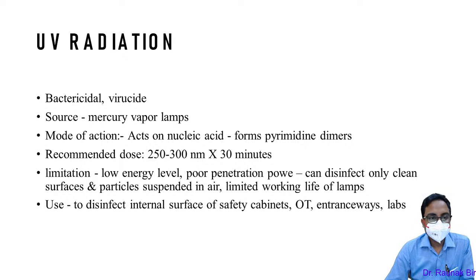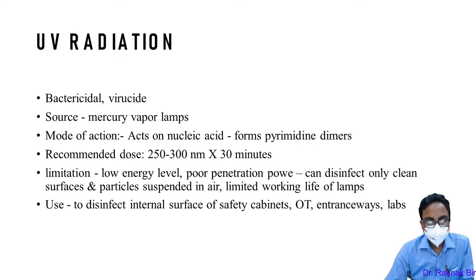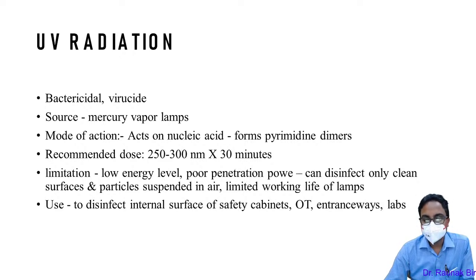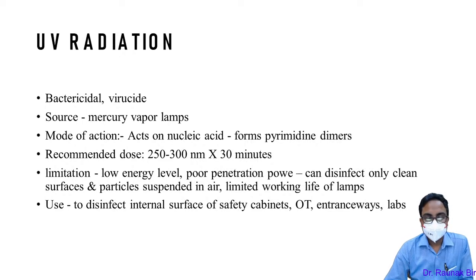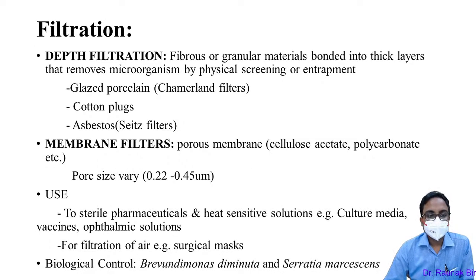UV radiation is bactericidal and virucidal. The main source is mercury vapor lamps. Its action causes damage to nucleic acids by producing pyrimidine dimers, rendering pathogens dead. Recommended dose: 250 to 300 nanometer wavelength for 30 minutes. Limitations: low energy level, poor penetrative power compared to gamma rays, can only disinfect clean surfaces, limited working life of the lamp. Used to disinfect internal surfaces of cabinets, OTs, entrances, and labs.